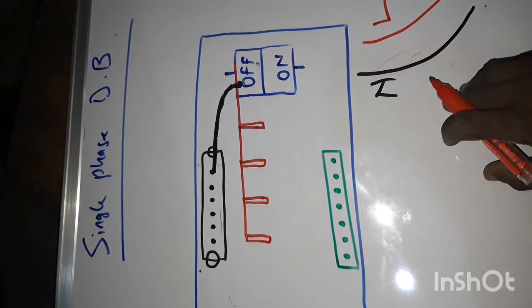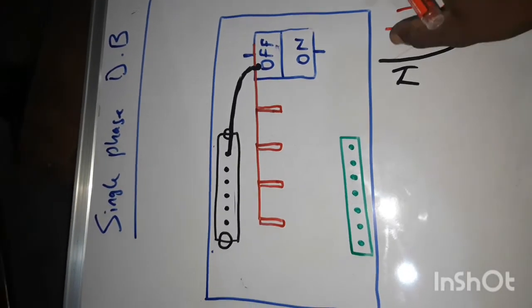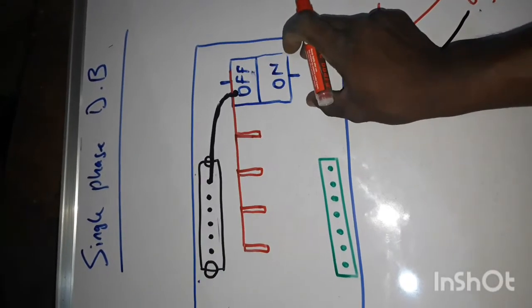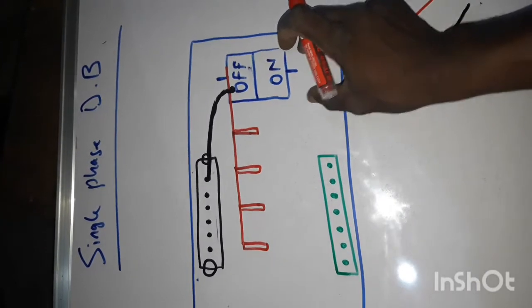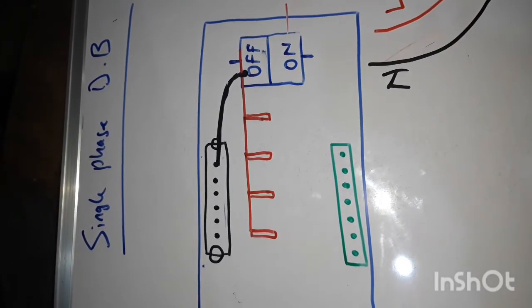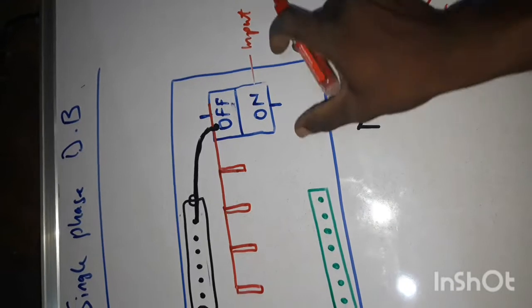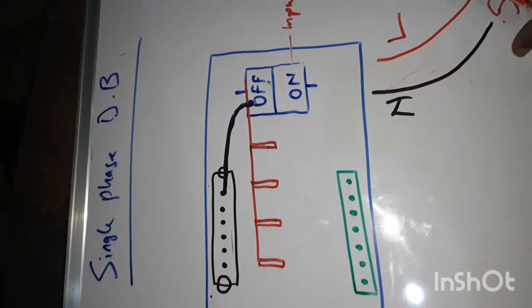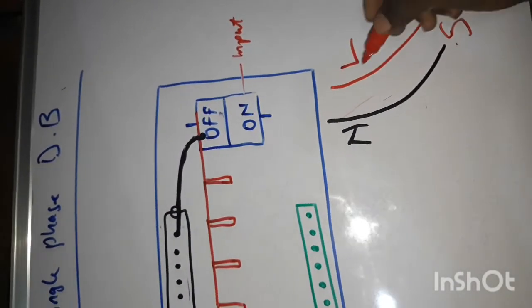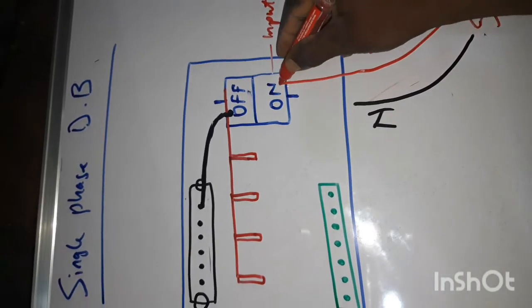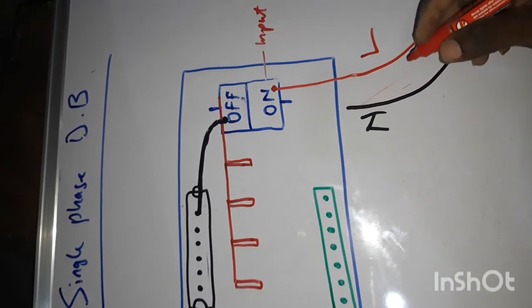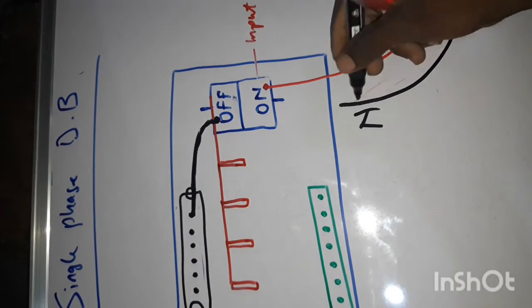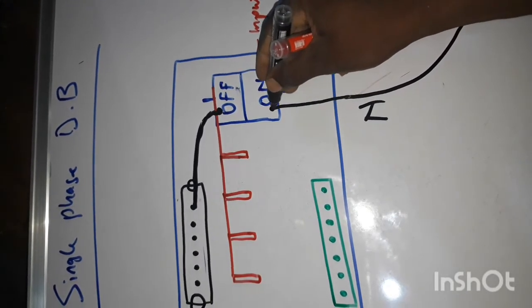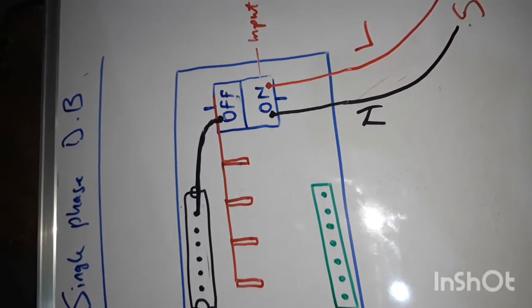So as you can see from this diagram, this side, which is this down part, is considered as the input. This side is considered as the input of your supply. So when your supply is coming from your changeover switch, the live wire goes to one side of the breaker, and the neutral also goes to the other part.